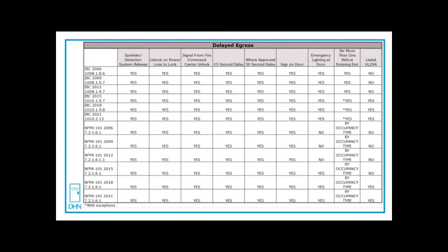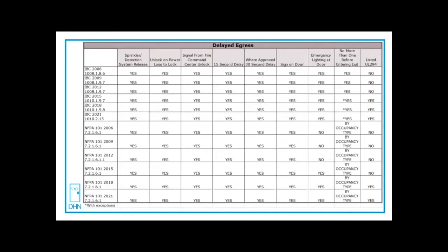That's typically reserved for healthcare occupancies. And if you look at this table, we're comparing IBC 2006 through IBC 2021 and the requirements for delayed egress. Also, NFPA 101 through 2006 through 2021 edition. So depending on what state you're in, you may have one of these codes or two. If you have more than one, the more restrictive requirements would apply.